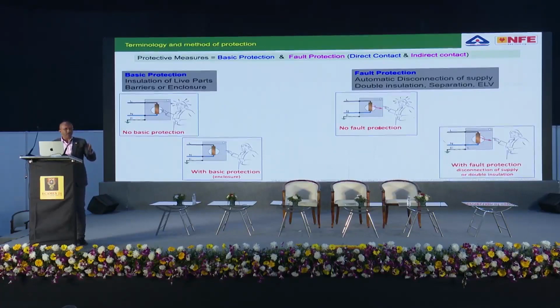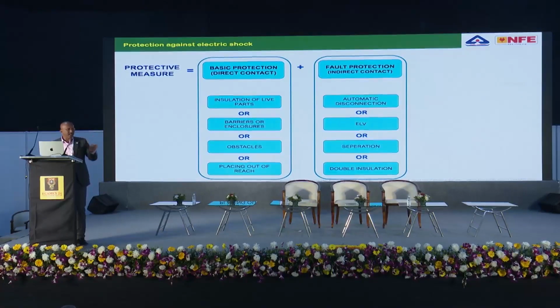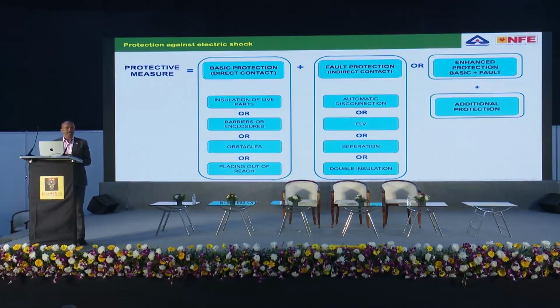So you need basic protection, you need fault protection. For basic protection, there are several measures. For fault protection, there are several measures. Then sometimes we need enhanced protection, both a much stronger protective measure and additional protection. So basically, this is the concept of shock protection. But once we go deep into it, this subject alone needs to be understood very deeply to implement or to design an electrical installation.